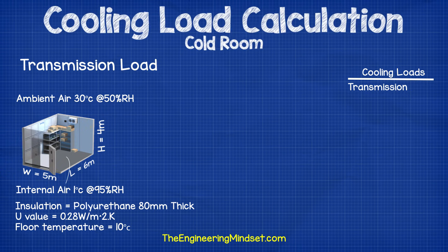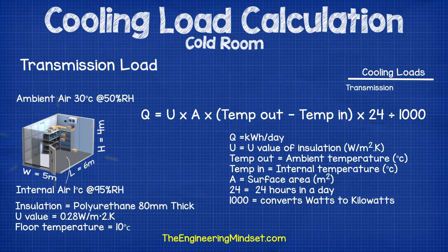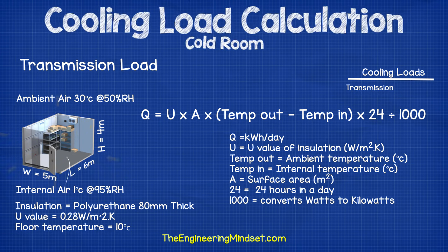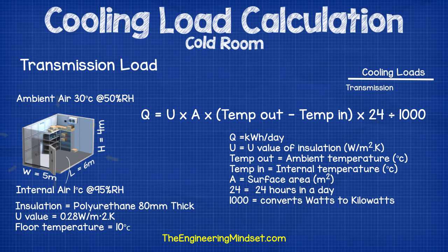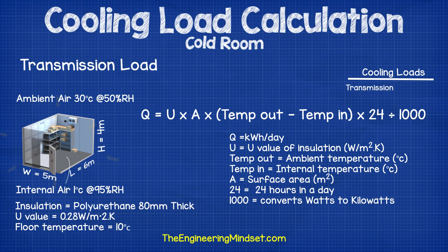The manufacturer should tell you what the U-value is for the insulation panels; if not then you will need to calculate it. To calculate the transmission load we'll use the formula: q equals U multiplied by A multiplied by (temperature out minus temperature in) multiplied by 24, then divided by 1000. The U-value we already know. A is the surface area for the walls, roof and floor. The temperatures we already know. 24 is the hours in a day and we divide by 1000 because we want the answer in kilowatts.